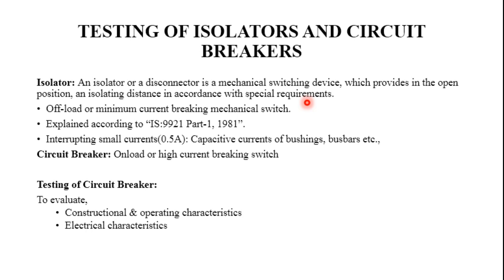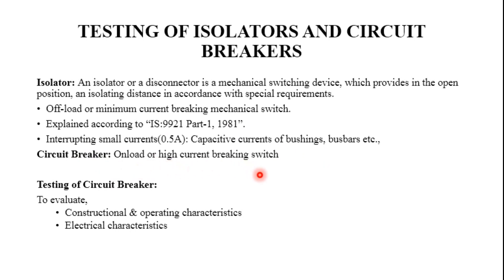The isolator is also capable of carrying current under normal circuit conditions and carrying a specified short-time current under abnormal conditions such as short circuits. This is further detailed by IS 9921 Part 1, 1981, and is subject to a small current limit of 0.5 A. The circuit breaker, by contrast, is an on-load or high-load current breaking switch.